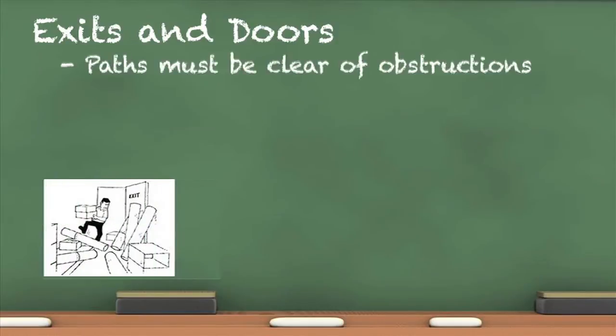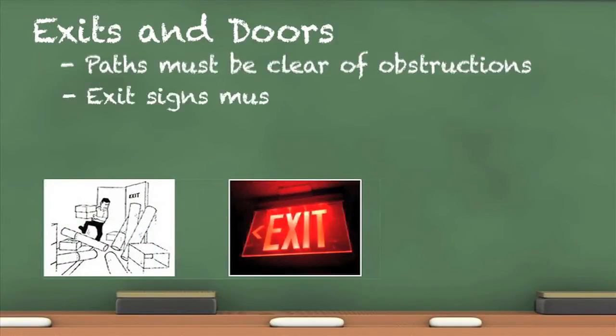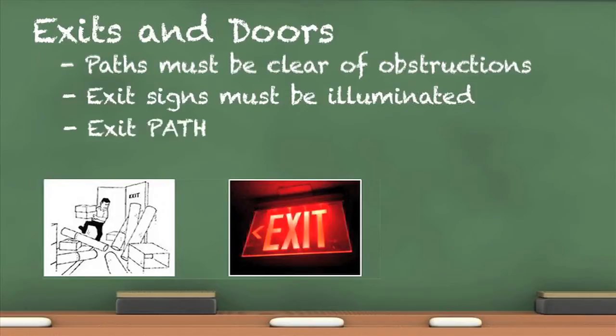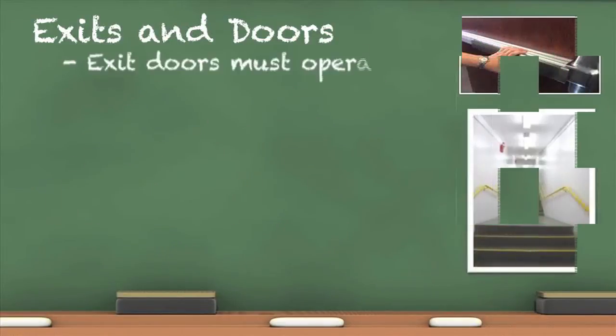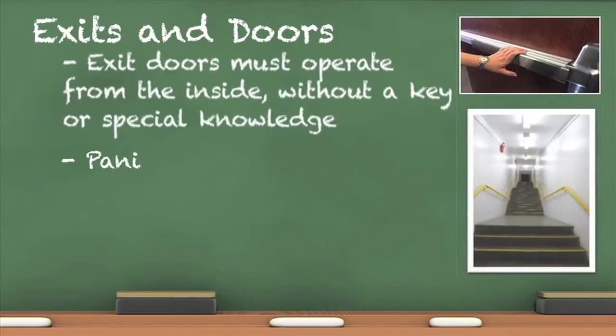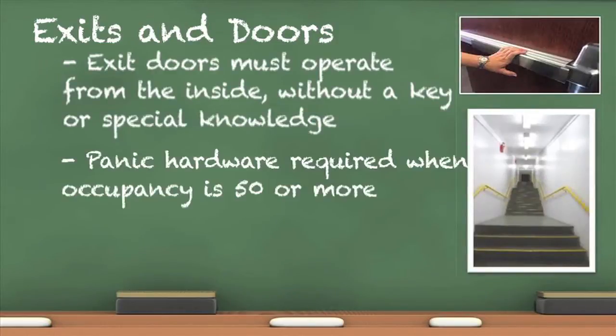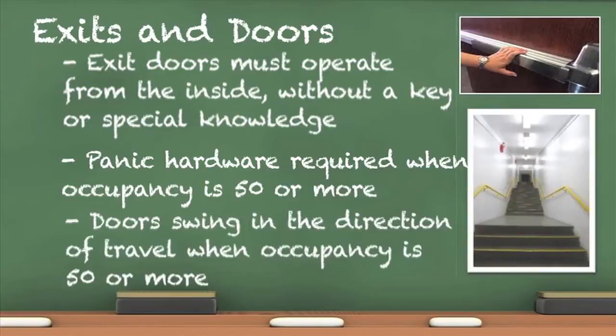All exit paths and doors must be free of all obstructions. Pay attention to the exit signs — they must be illuminated at all times and all bulbs must be working. The exit signs must be clearly visible from a distance. The exit path is required to be illuminated, and emergency lighting must be capable of illuminating when there is no power. The ability to leave an occupancy quickly and safely is crucial. All doors and door hardware must function properly.